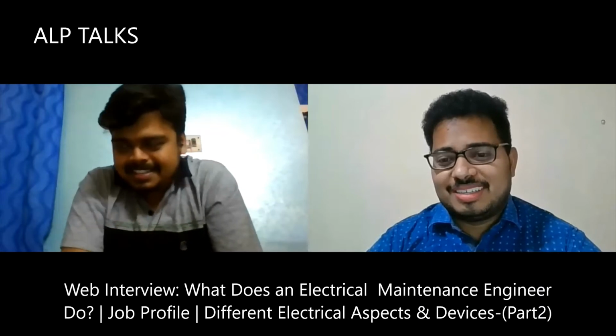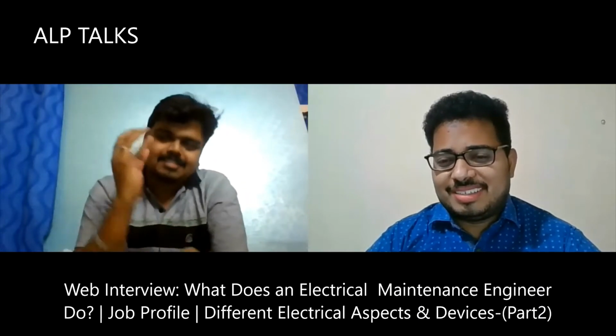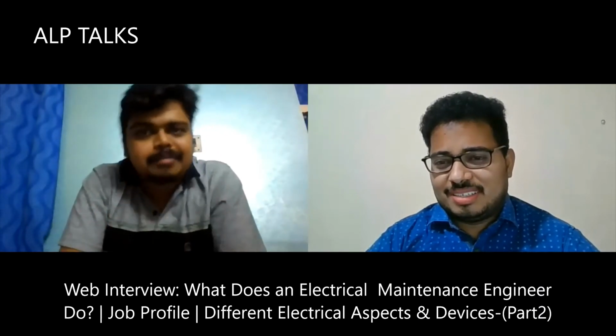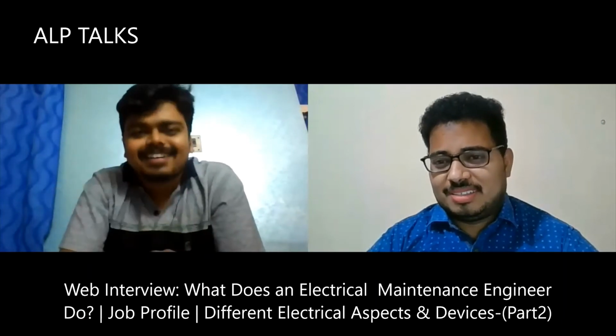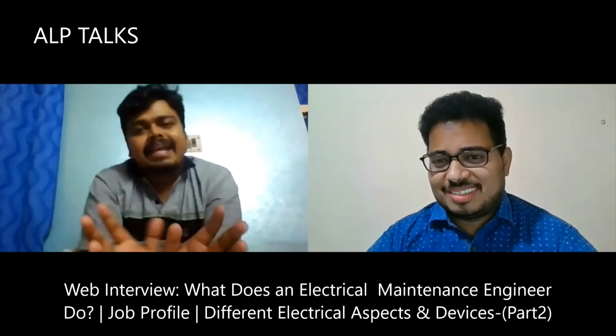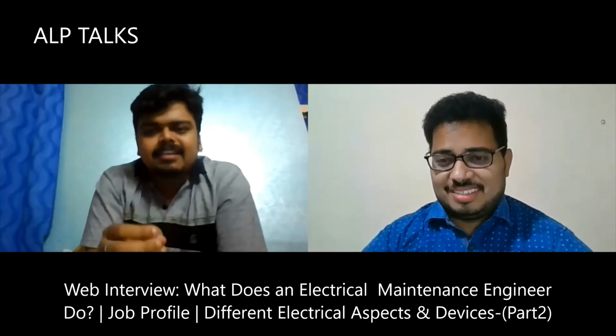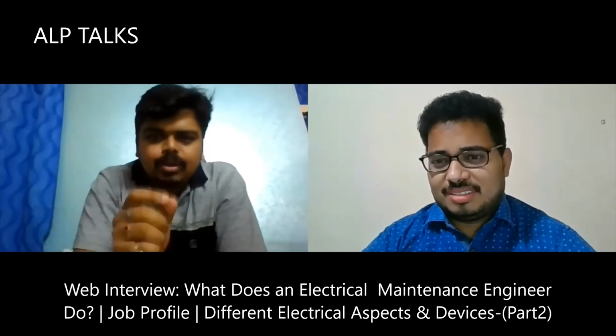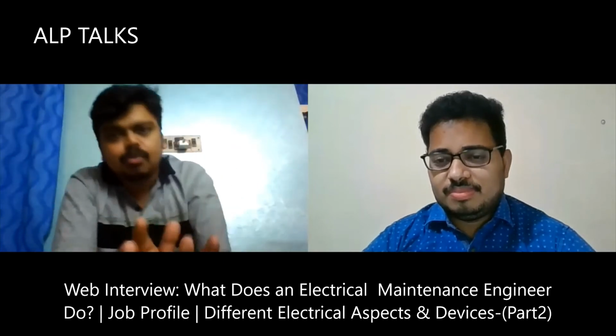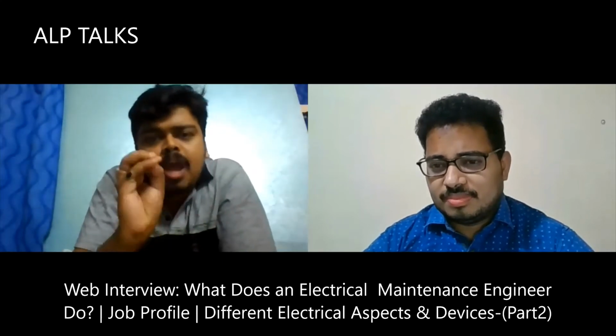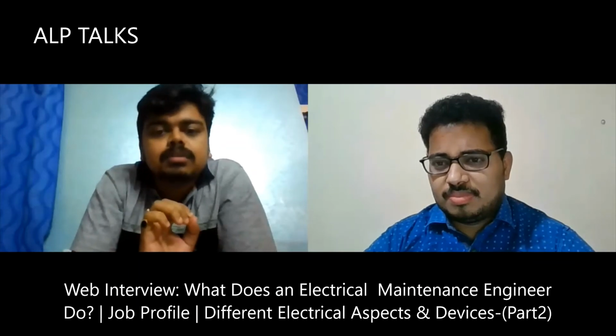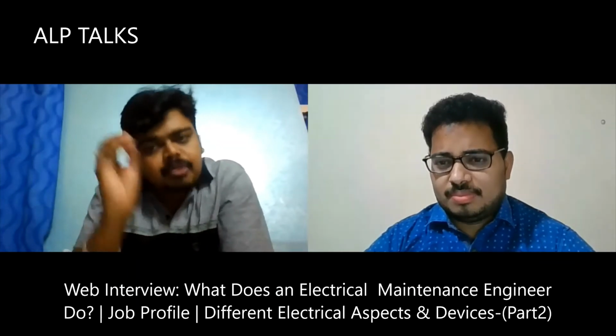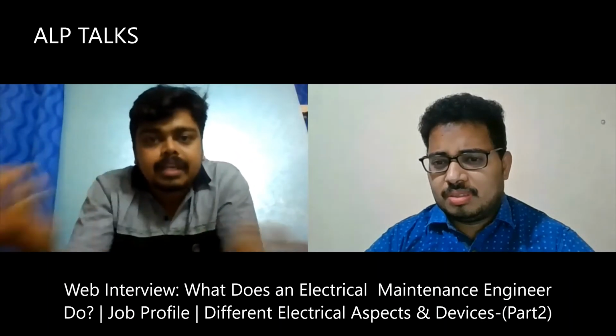Honeywell gas detector I commissioned by myself in every plant - 4 plants I commissioned in my own hand - the programming, testing, methane testing, regulating, checking, and also smoke detector, heat detector. Not only the smoke detector, because in the UPS room we have to put the heat detector, and in the battery bank room we have to put the heat detector. Otherwise you can't know at night time if any incident happens or not.